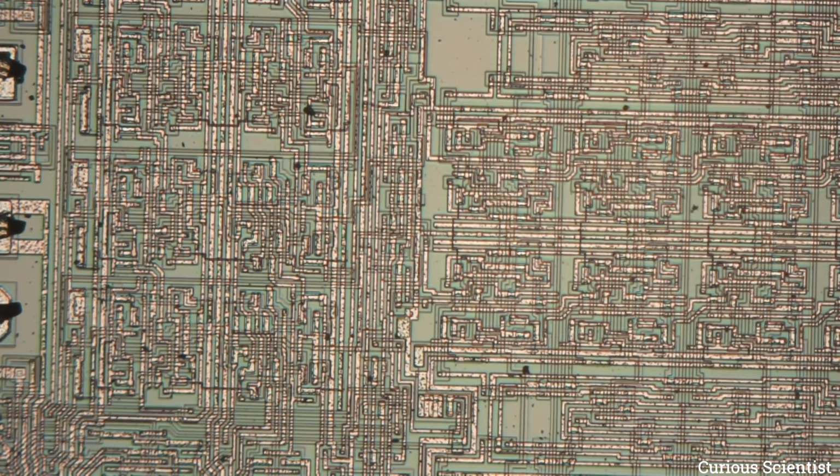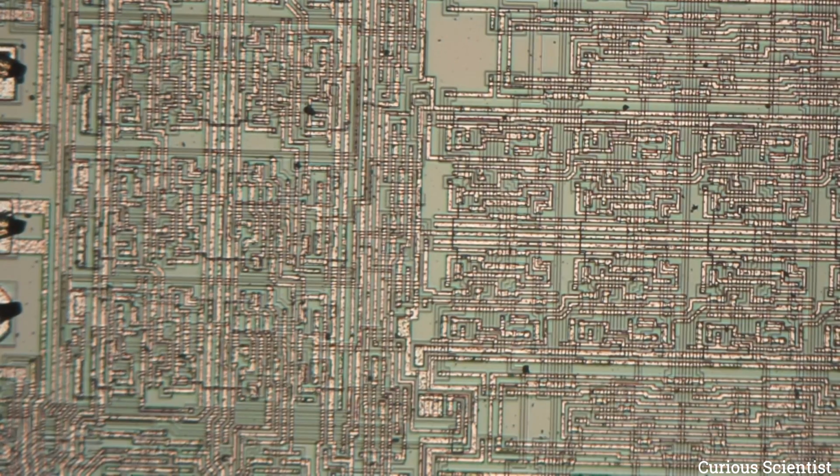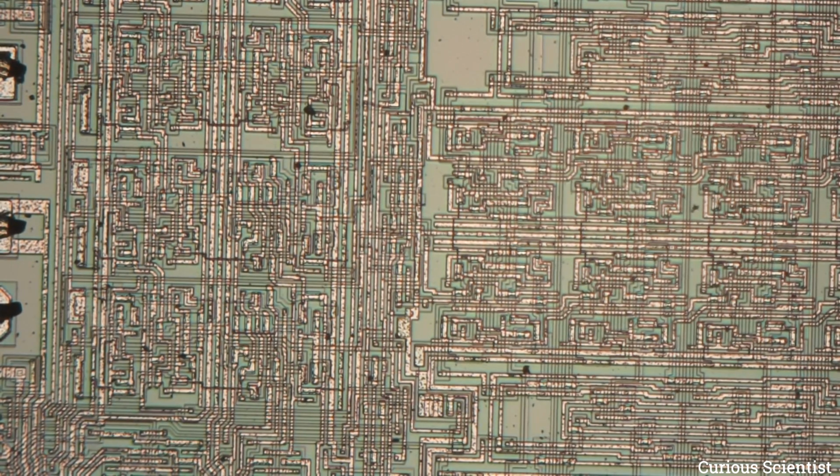So you could see that I could focus it more or less easily with the joystick. But actually I made the slow mode of the button exactly for this. So let me select that. So now I'm in button mode and hopefully the slowest mode is activated. And I'm moving on the Z-axis, so let's see how the system behaves. So we go out of focus. And now it's more or less focused. So you can see that with the button it's even easier.